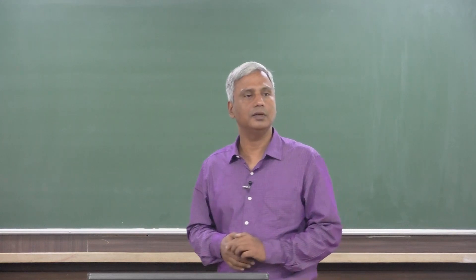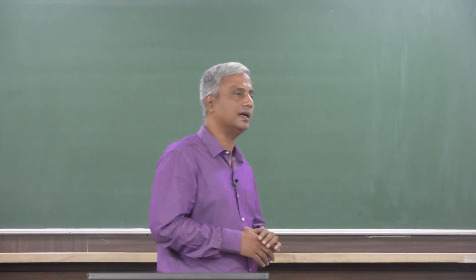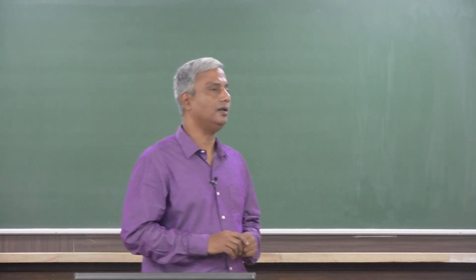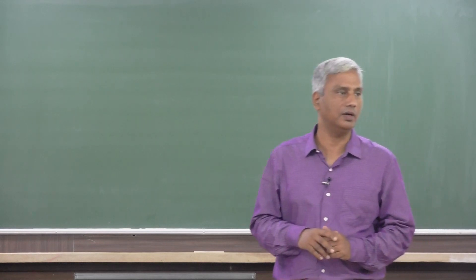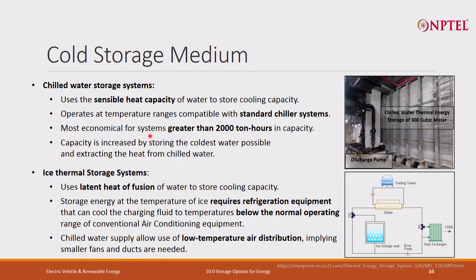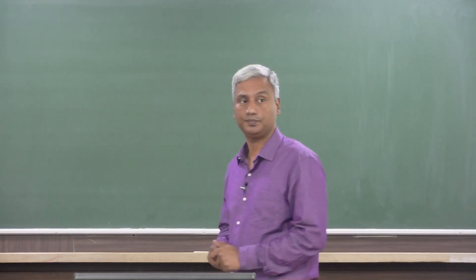The return water temperature is 20 degrees, meaning if my whole tank is at 6 degrees, whenever I have excess renewable energy I can circulate this chilled water to the whole building for the HVAC unit and the return water temperature comes to 20 degrees. The energy storage capacity is: E = m · cp · ΔT, where mass of water is 3 lakh kg, cp of water is 4.2 kJ/kg/°C, and ΔT is the difference between return water temperature of 20 degrees and storage temperature of 6 degrees, giving 14 degrees. Multiplying all those values gives the thermal energy storage capacity.